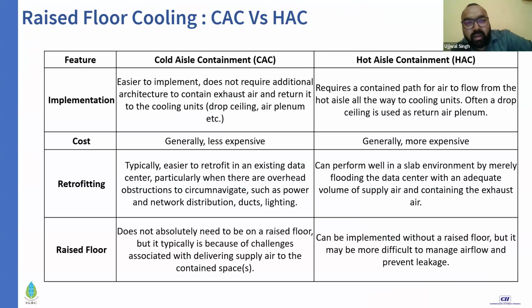The cold aisle is very easy to implement compared to hot aisle, and it is generally less expensive. So if budget is your primary concern, I would recommend going for cold aisle containment. Also, if you have a lot of retrofitting taking place in your data center, and on day one your full hall will not be loaded with equipment, it's very easy in cold aisle to just add one more row after the other. So when you talk about modularity, cold aisle containment is the better option.